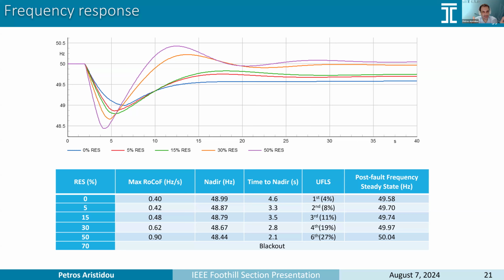And if you want the rate of change of frequency, you need to take different measurements and then compute it. So already this frequency measurement could take 100 to 200 milliseconds to get a good estimate of the RoCoF. So even if you trigger a supercapacitor, you will need to do that after you have done the measurement and gotten a good estimation of the RoCoF. Yes, the supercapacitor is faster to connect and faster to discharge. However, you still have the delay from the measurement and the computation.